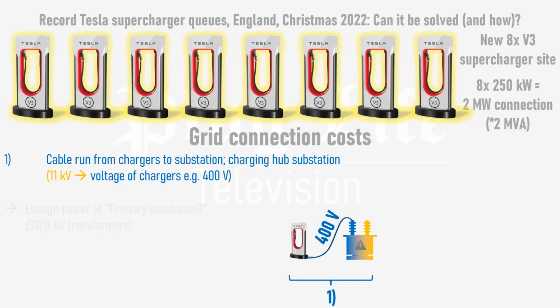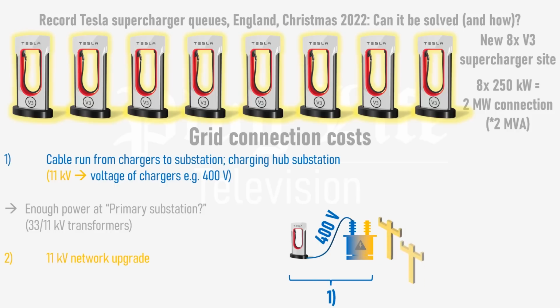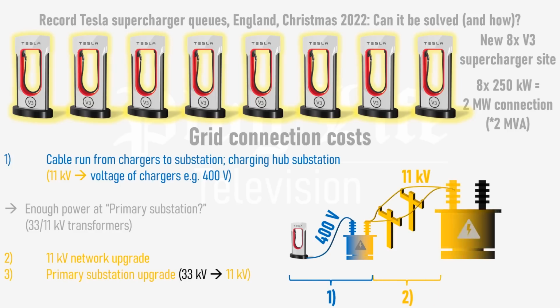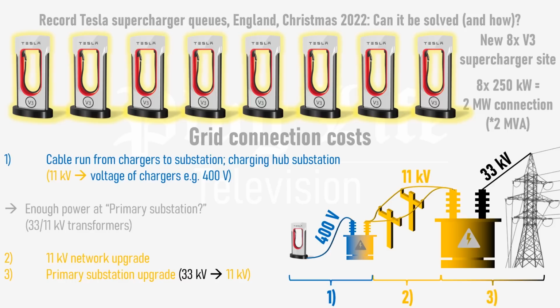But what if the local distribution grid doesn't have enough spare power? Then the 11 kilovolt network will need to be upgraded to accept higher power, and a new primary substation will need to be built to convert more power to 11 kilovolts from the 33 kilovolt transmission grid.